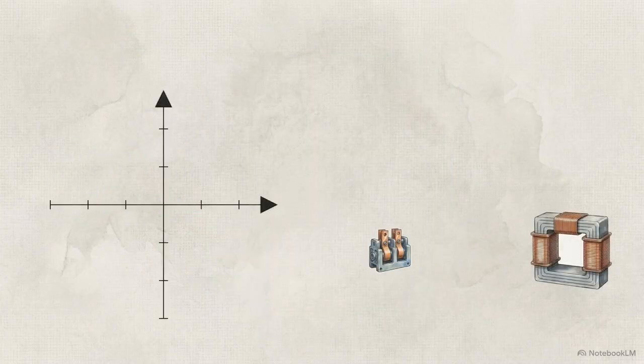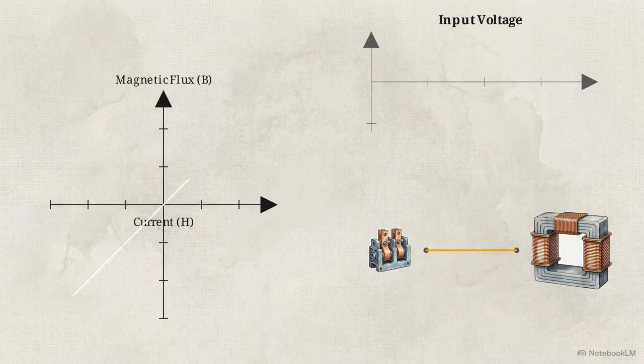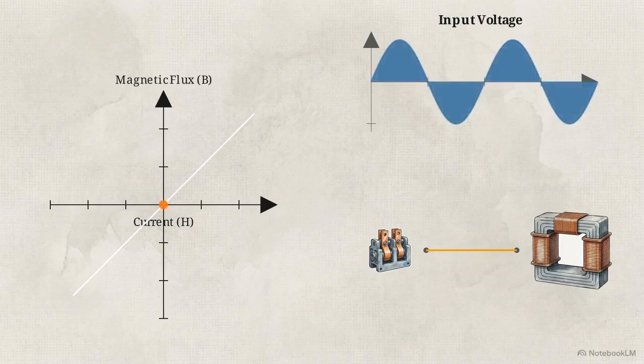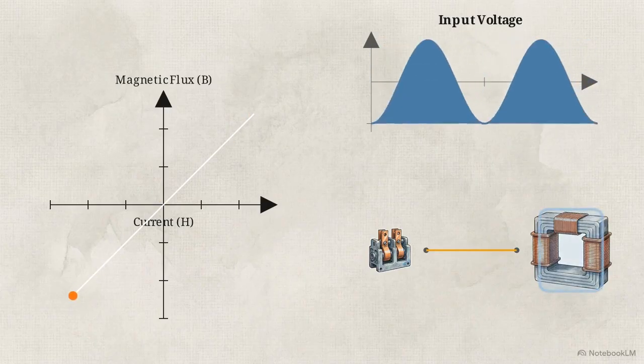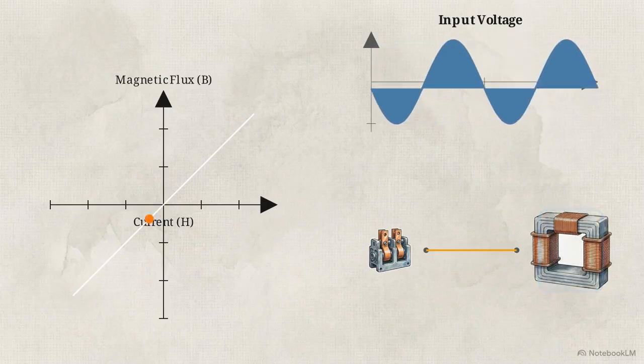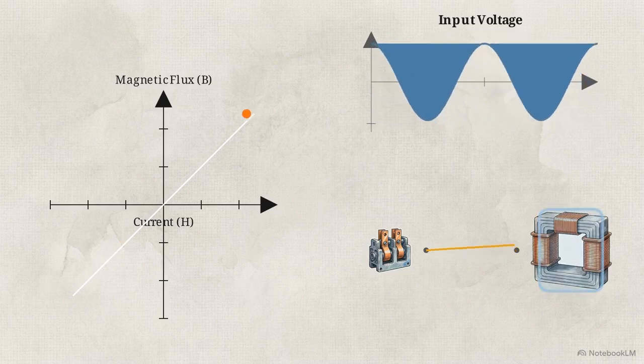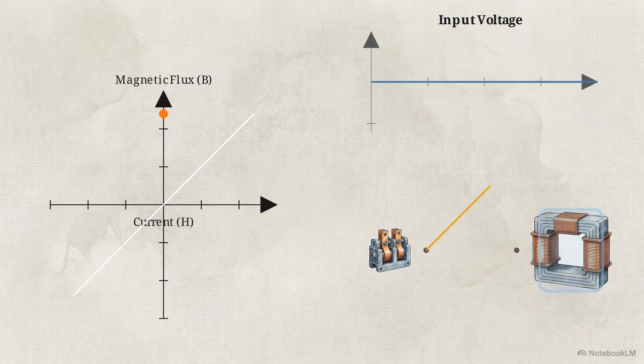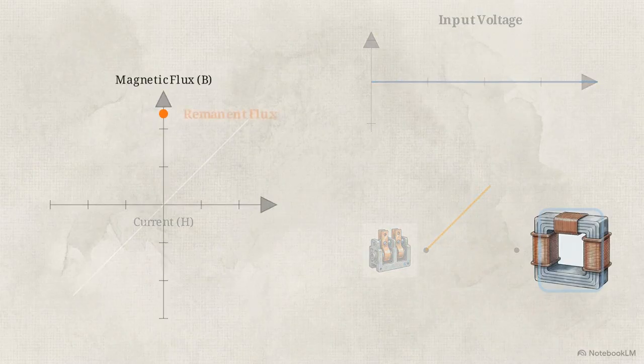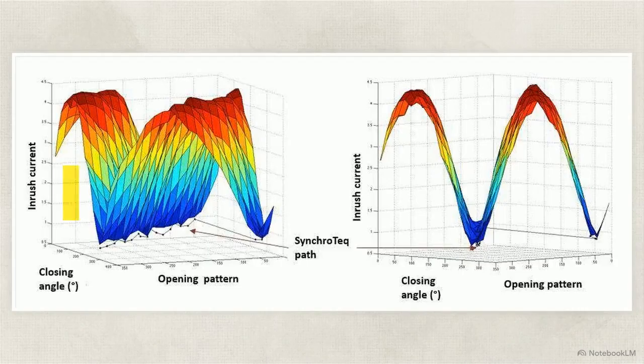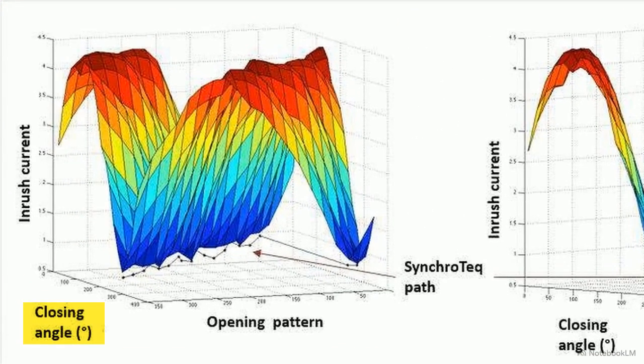The relationship between the magnetic flux in the core and the current required to generate it is described by the BH curve. Under normal operation, this relationship is mostly linear, but when a transformer is disconnected, the voltage wave stops, and the iron core retains a magnetic memory of that final moment. This trapped magnetic field is known as remnant or residual flux.